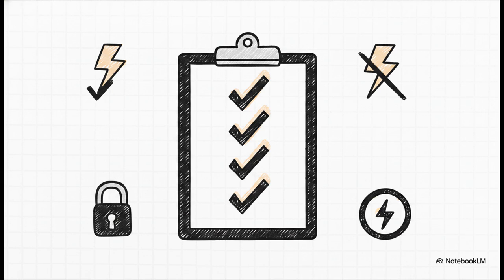First off, we are exclusively talking about low voltage here, so no high voltage equipment is covered in these specific guidelines. Second, everything is anchored right to the AS/NZS 3000-2018 wiring rules. But honestly, the most vital point here is that a safe system of work absolutely must be in place before you even think about starting a test. We're also dealing specifically with installations using a multiple earth neutral or MEN system. You just have to know exactly what kind of environment you're walking into before you begin.